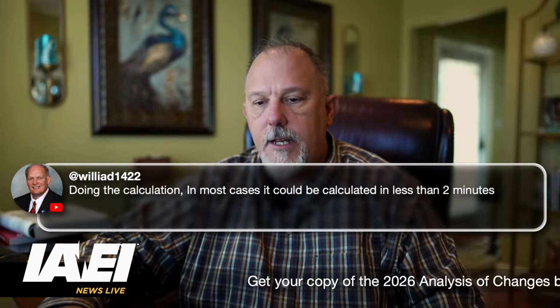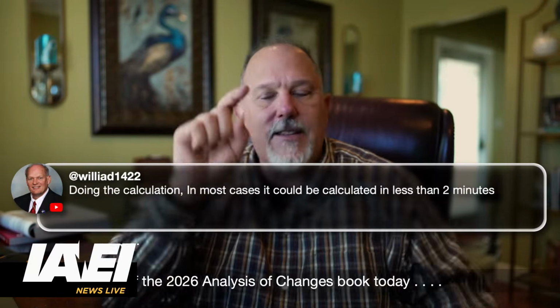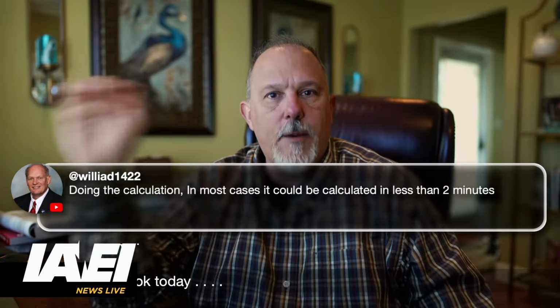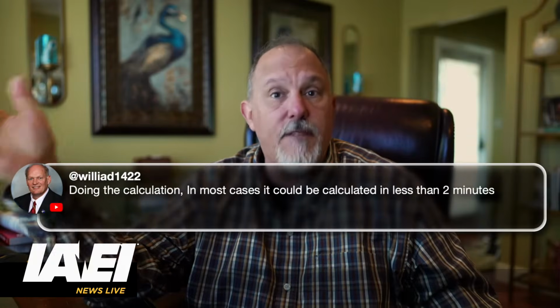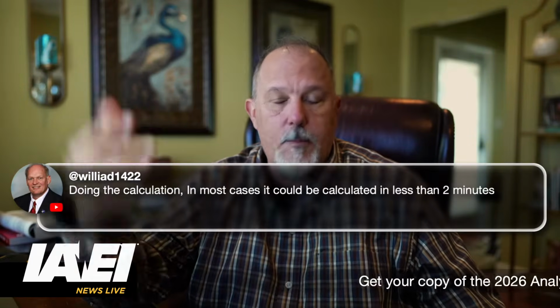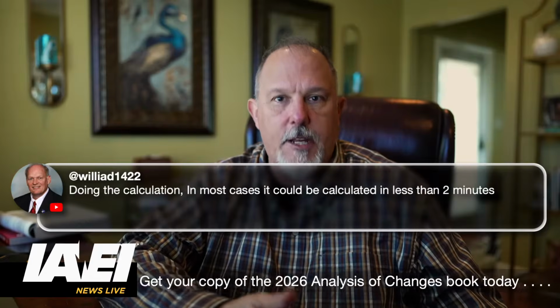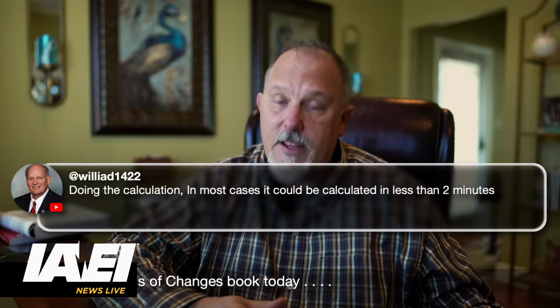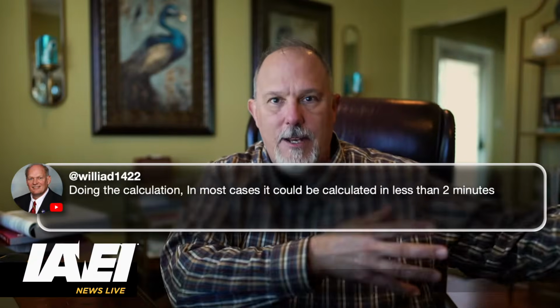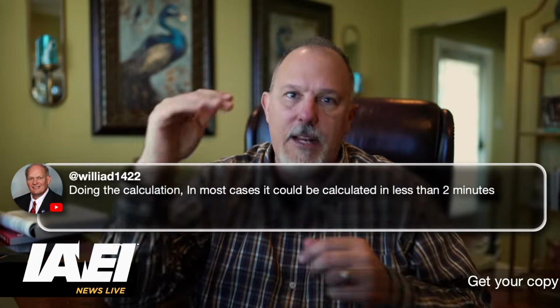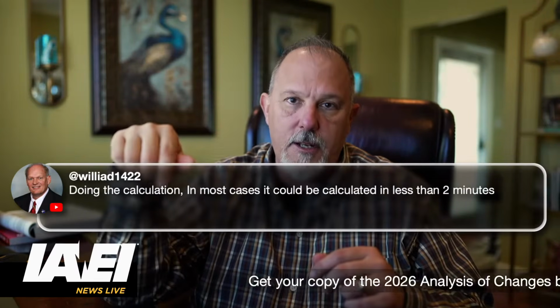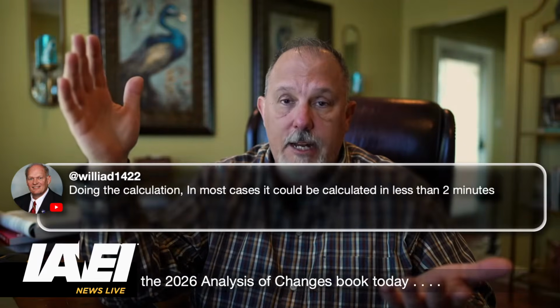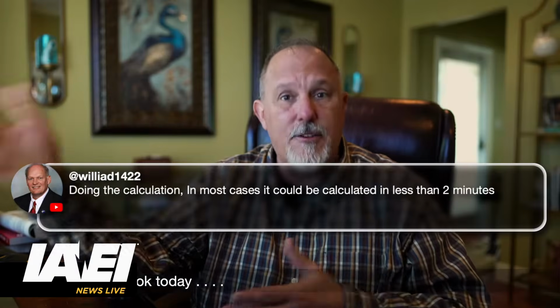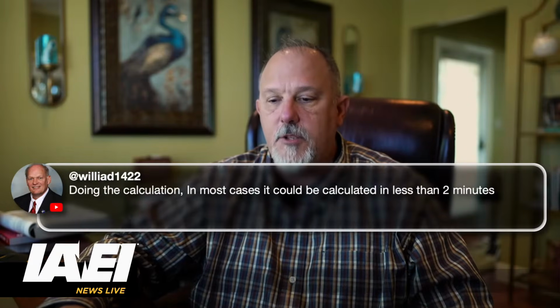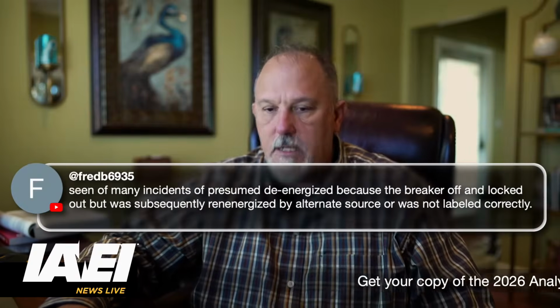Yep, Willie's live, dead, live. Doing a calculation, in most cases, it could be calculated in less than 2 minutes. Yeah, I would. In fact, David, here's my thoughts on that. Because you already have to do the short circuit study, you've got to calculate fault currents at all these data points anyway. You're more than likely going to use a software application to get that done, and you're going to have to have a qualified person to do that. If you've generated the one-line diagram, the only other missing piece of the pie would be the coordination. But incident energy is based upon the upstream clearing time plus the downstream fault contributions, and you can make some assumptions there. So it's not as hard as people think it is.